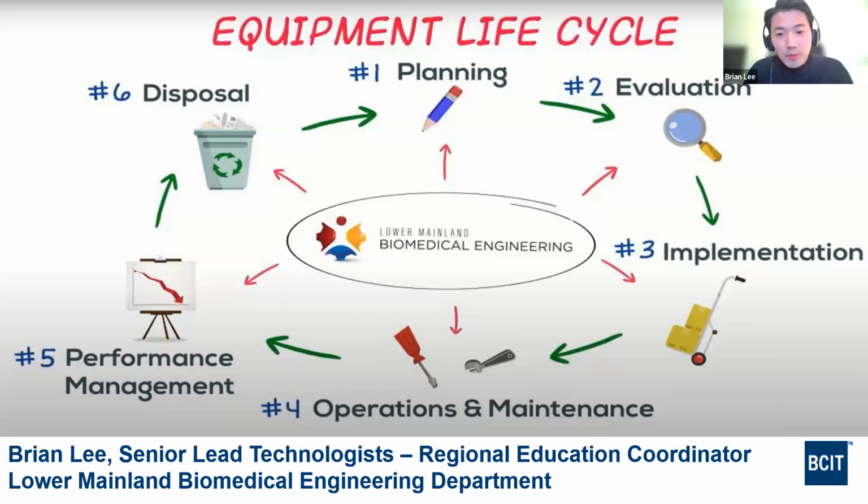And what services do we offer? The screen we are seeing right now gives you the life cycle, which is basically the services that we cover. First, planning and procurement. When the doctors are purchasing new devices, as biomeds, we provide technical consultations and evaluations, and do implementations and installations in the hospital upon purchase.